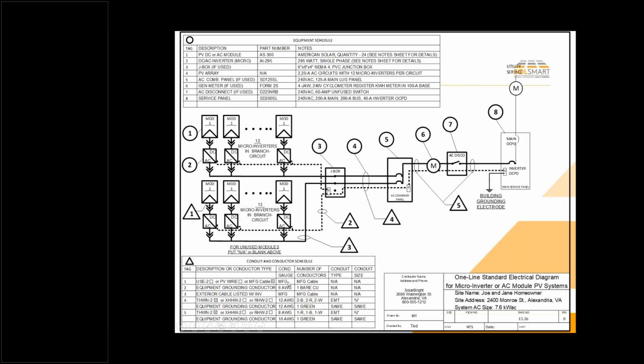That's very common for microinverter systems. And then it has manufactured cable to bring all that into a J box, a junction box here, where we transition the wire to a conduit wire, which is going to be that THWN-2 wire going into our AC combiner panel with 2 20-amp circuit breakers. And those 2 20-amp circuit breakers get combined together and go into one 40-amp circuit breaker into the 200-amp panel, just like the other project.